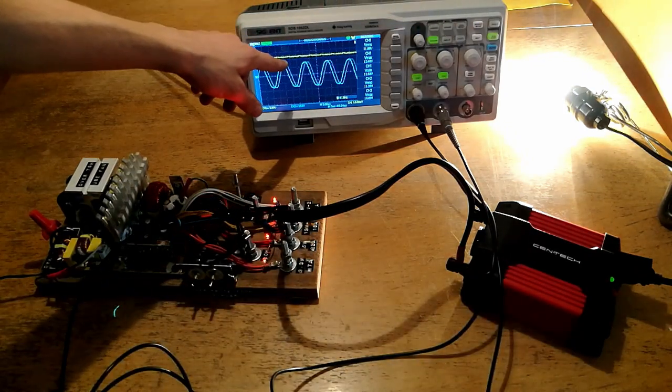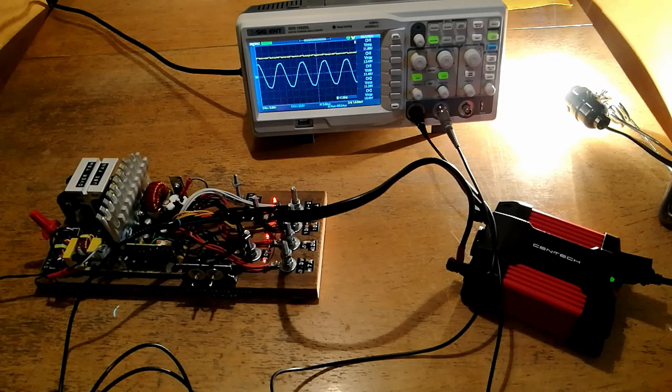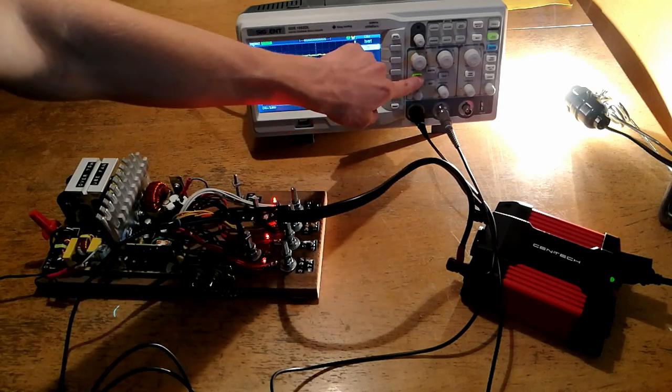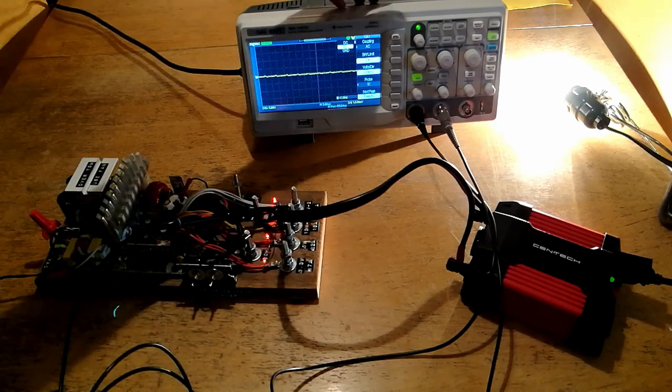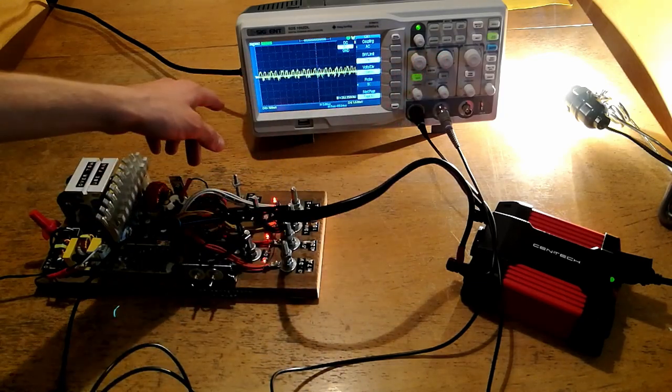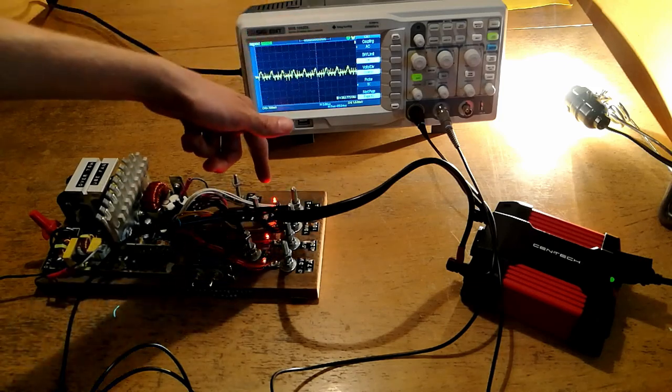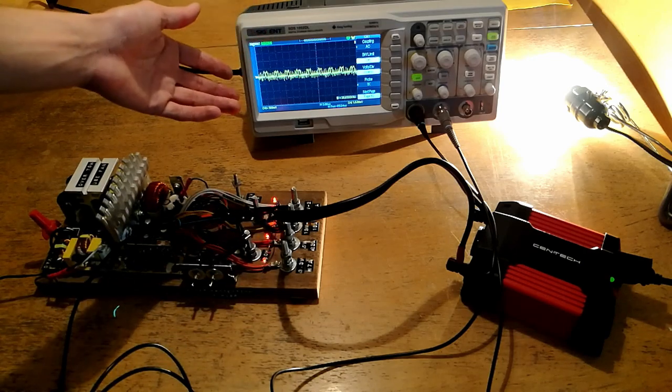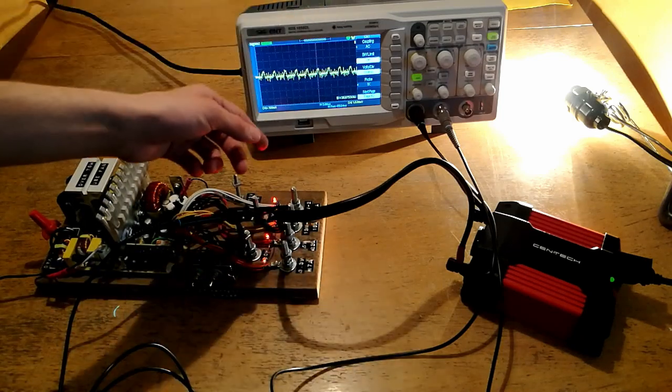waiting for it to kick on. Now the light bulb is on. As you can see there's a fair bit of ripple and this corresponds roughly to the switching frequency at the output of the inverter where it's drawing in large amounts of current. In fact if I wanted to I could even go in, turn off channel 2, and then I could switch channel 1 to an AC couple like so and then zoom in my vertical and that would allow us to see all the noise on this power line. This is obviously reflective of the bad capacitors on this power supply because we're getting all this ripple at the output as a result of the capacitors having a hard time maintaining that stable output.